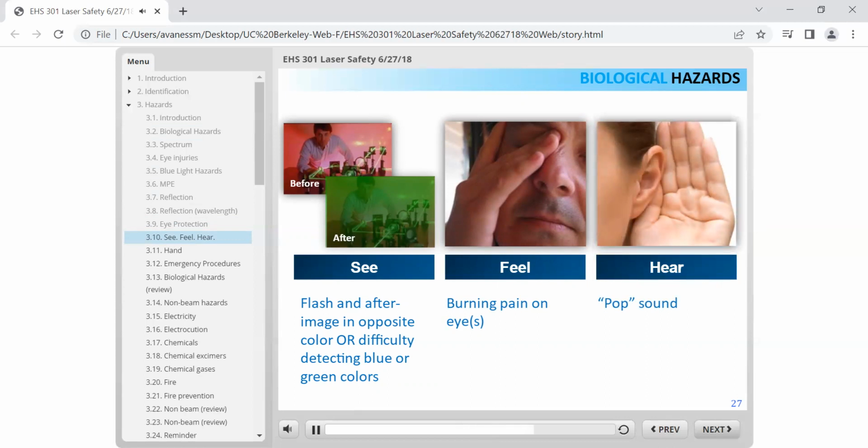Visual disorientation due to retinal damage may not be apparent to the operator until considerable thermal damage has occurred. Exposure to a Q-switched neodymium YAG laser beam is especially hazardous and may initially go undetected because the beam is invisible and the retina lacks pain sensory nerves.